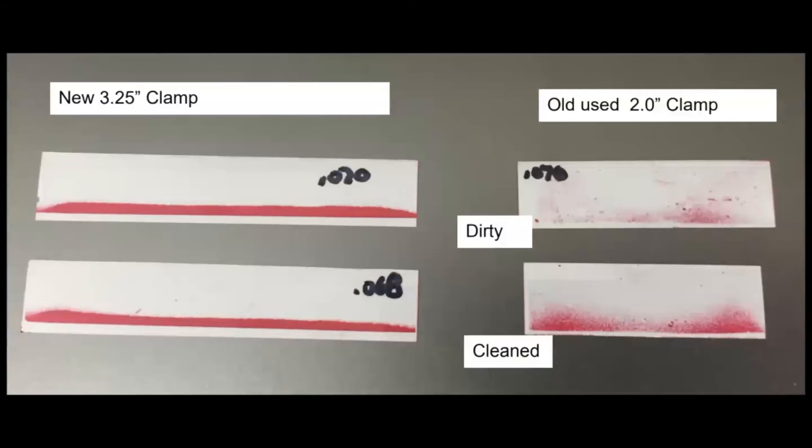The current design has a large moment in the middle of it, causing it to deform and allow debris to get in between the electrical contact bases, causing variations in each clamp's resistance. This can cause a lot of damage, resulting in a loss of contact as seen in the pressure paper. Owens Corning has tasked us with redesigning the clamp to last longer and maintain better contact.